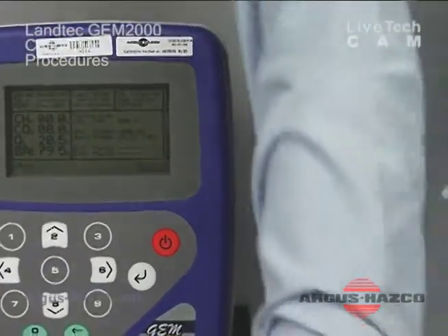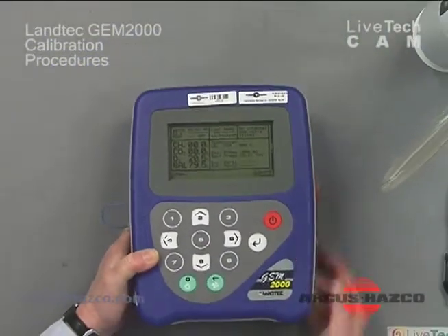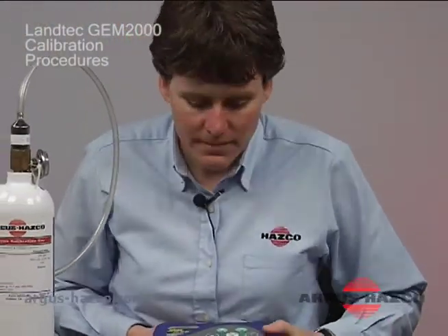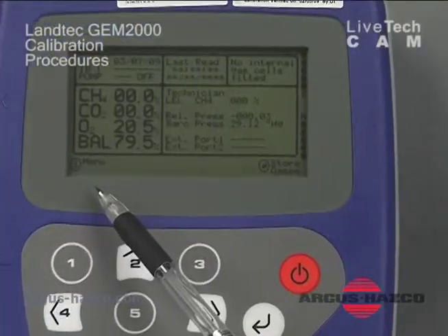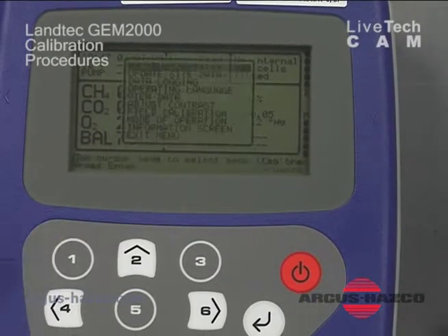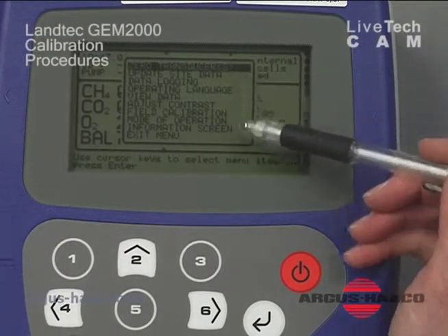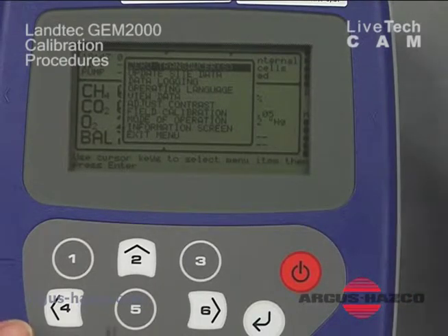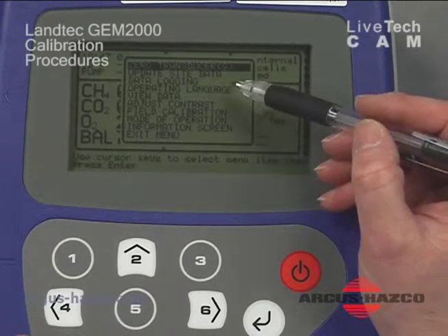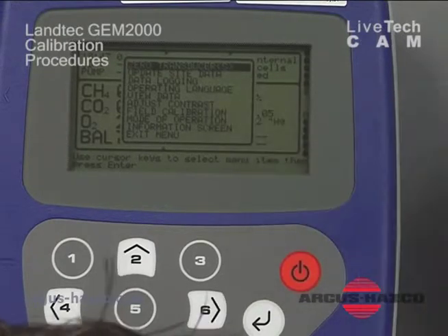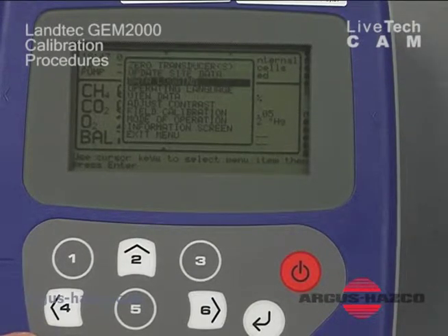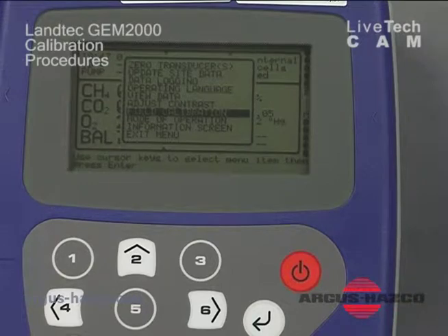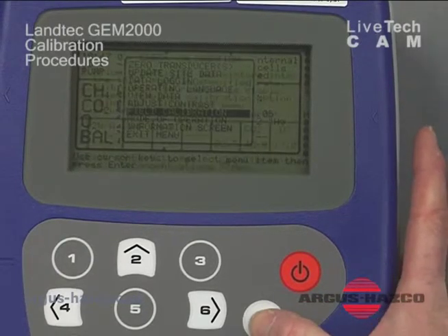Now to calibrate this unit, we already have our calibration cylinder ready to go. What we need to do is hit our number 1 button, go into menu, and then we'll have a sub-menu or a sub-screen pop up. And the first one is zero transducers. We want to go ahead and scroll all the way down to where it says field calibration, so we use our arrow key. Highlight field calibration. We hit enter.